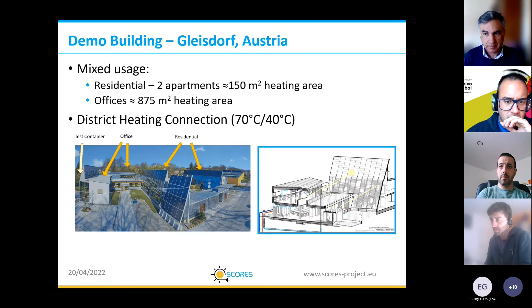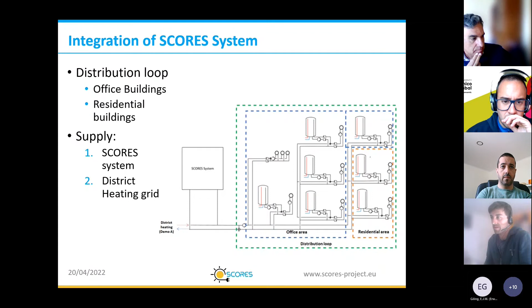The overall concept is that we commissioned a number of these SCORES technologies, such as the heat pump and PV system, to act as a second source. We see here the district heating connection, and as a second source of heat and electricity, we have our SCORES technologies. So essentially the main supply of heat for the buildings, office and residential, can either come from the SCORES system, and the district heating system is used as a backup where we don't have sufficient heat in the SCORES buffers.